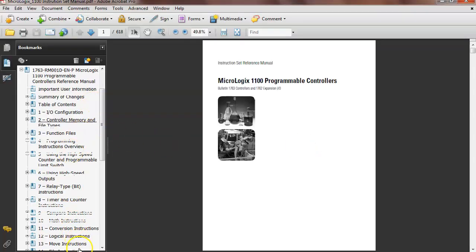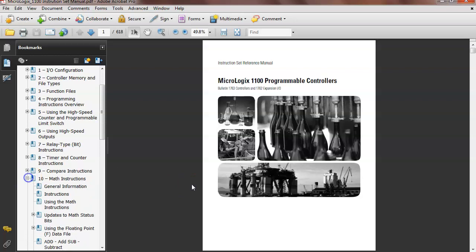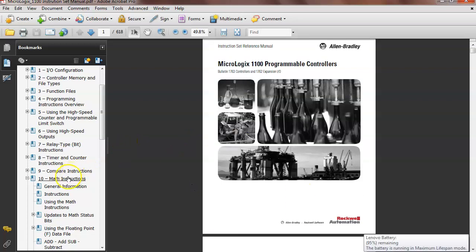So every one of these instructions takes time. And the more time you have, you could literally technically miss inputs. If the programs are long enough, you could miss real rapid inputs, because it wasn't in that scan. So you come up here and hit something real fast, and if it's not scanning that rung, you would bypass it. Yeah, we would miss it.